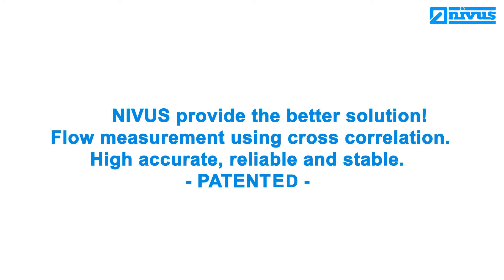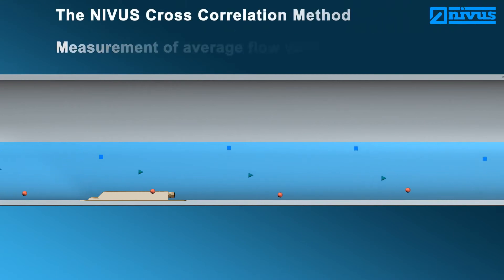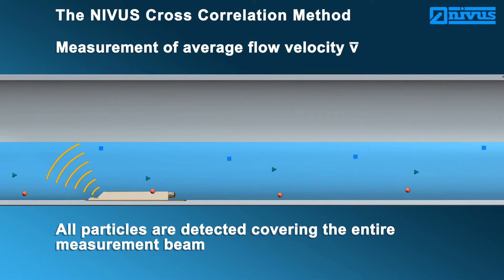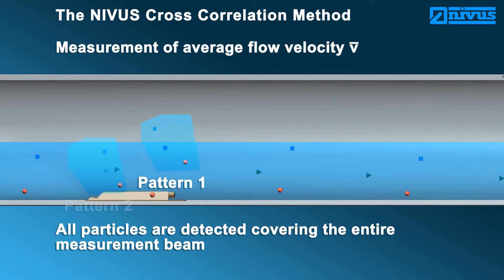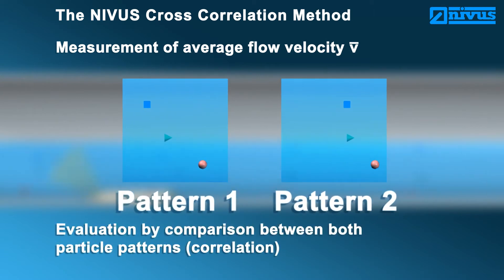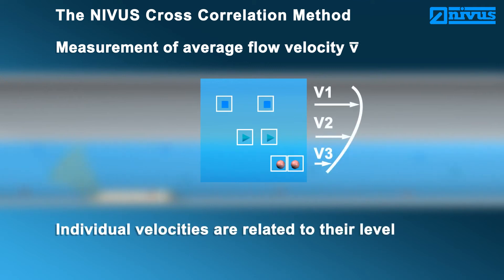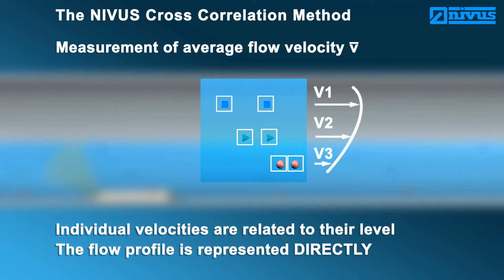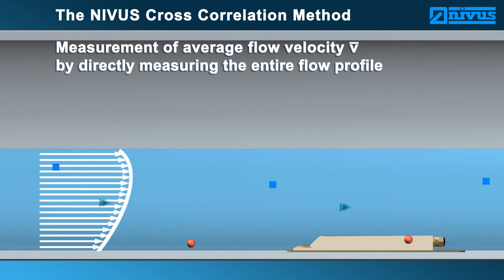NIVUS provides the better solution: flow measurement using cross-correlation — high, accurate, reliable and stable. The NIVUS cross-correlation method is not a spot velocity measurement. Here all particles are detected at the same time, covering the entire measurement beam. The particle images are evaluated by comparing correlation to each other, and this comparison repeats within a few milliseconds. In addition to the individual particle velocities, the relation to the flow level is available, making it possible to represent the flow profile directly. The discrete flow velocities related to the flow level, covering the complete measuring beam, ensures high, accurate flow metering.